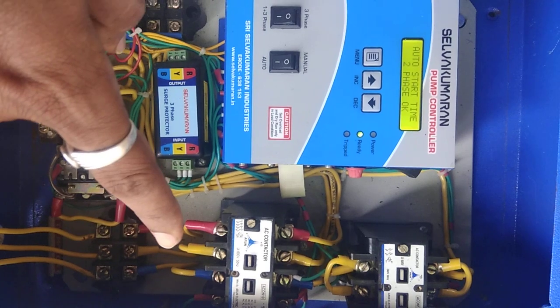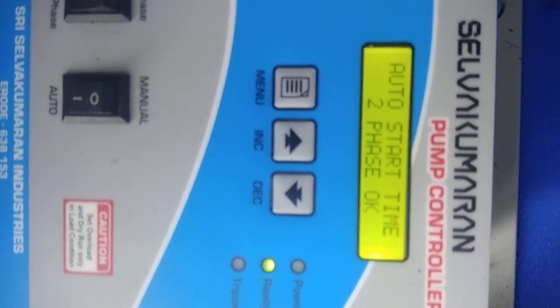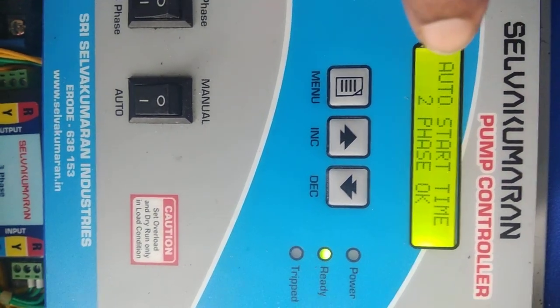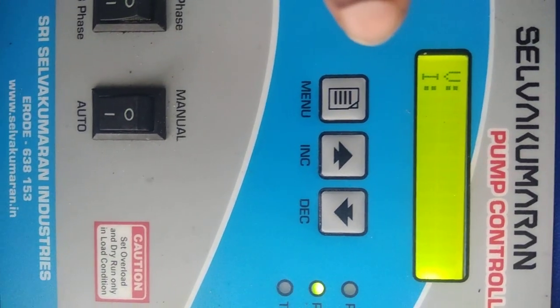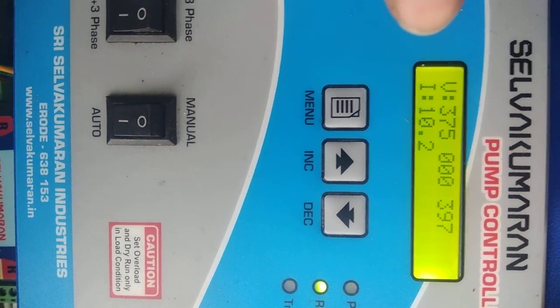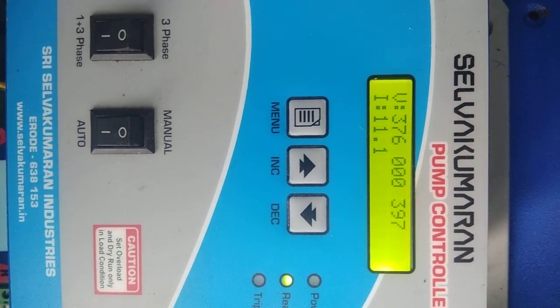Now the main contactor is on, and the controller will start the motor. It is auto-start at two-phase. The controller will display the voltage and current readings: 376, 00, 397, and 10.6 amps.